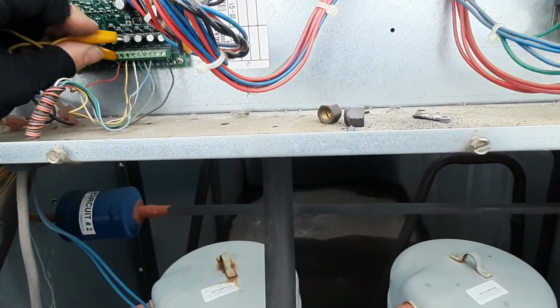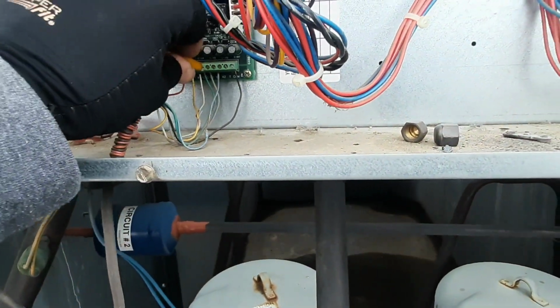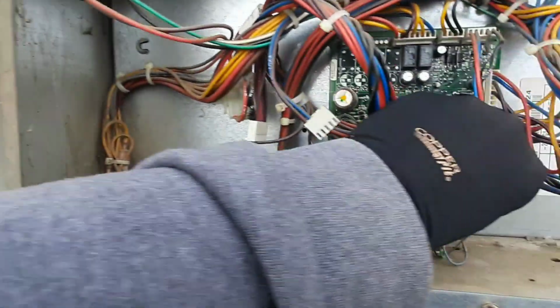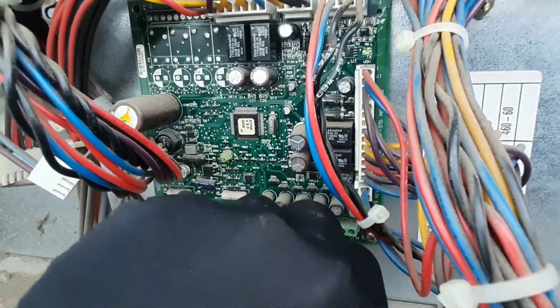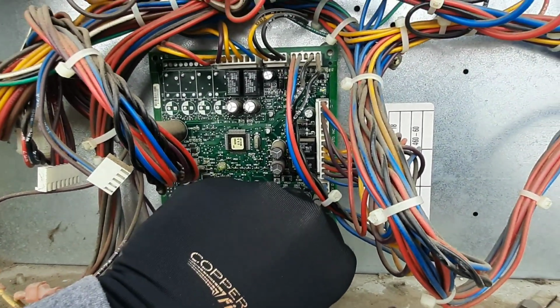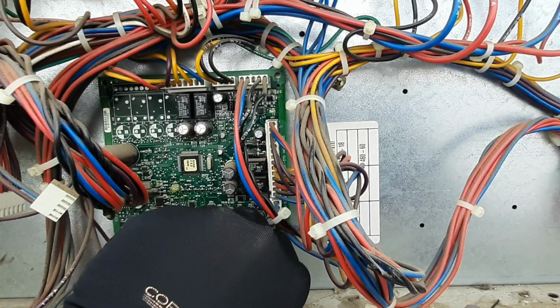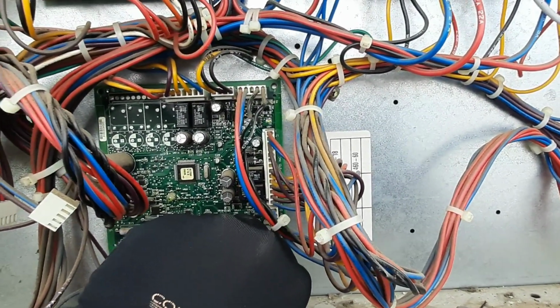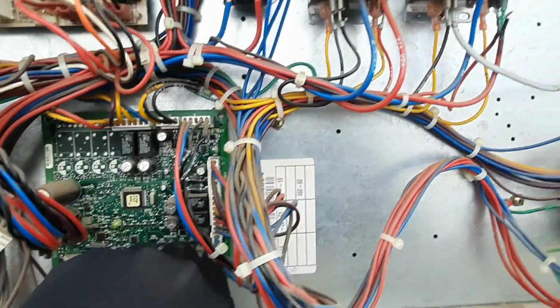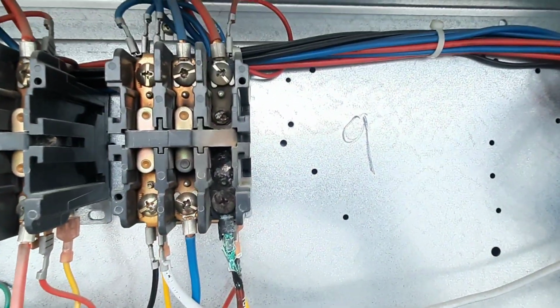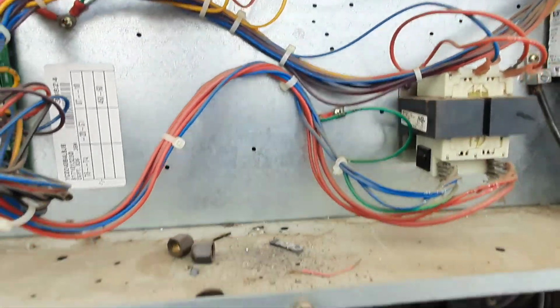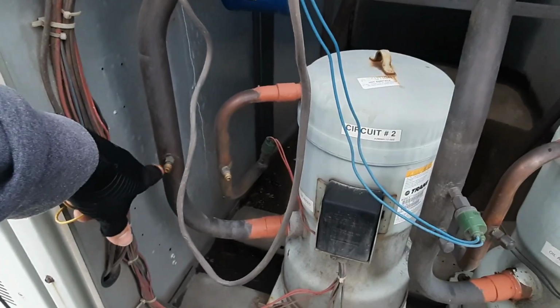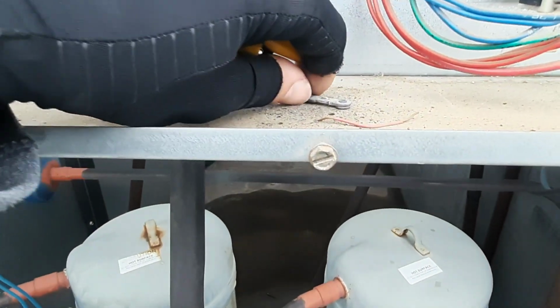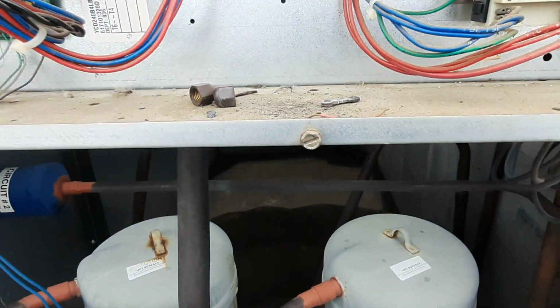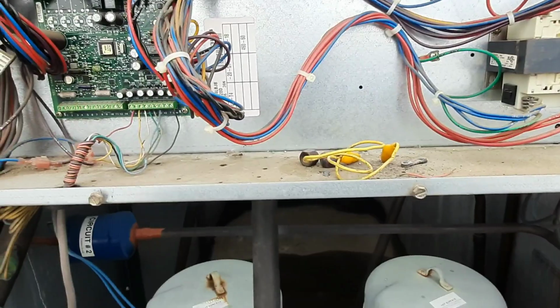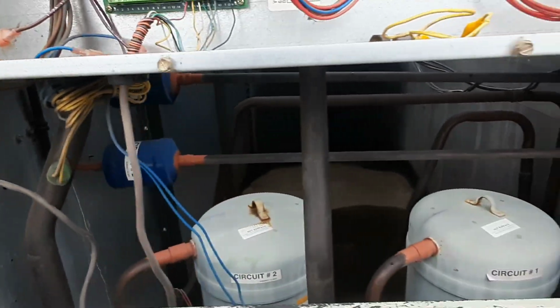So let's not jump common because that would be a bad idea. Let's jump red. And I'm getting nothing jumping my green blower. Lockout, it was warm yesterday, so lockout is probably something on the compressor side, maybe cooling lockout. Somebody's been in here. I got taps. There's your contact. So let me keep digging. Something weird is going on here.